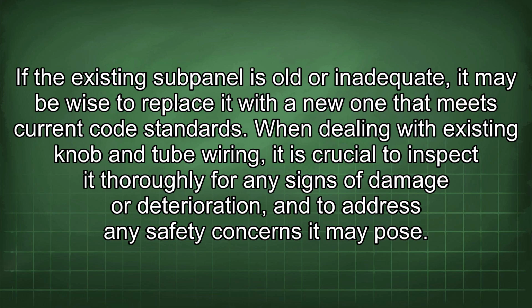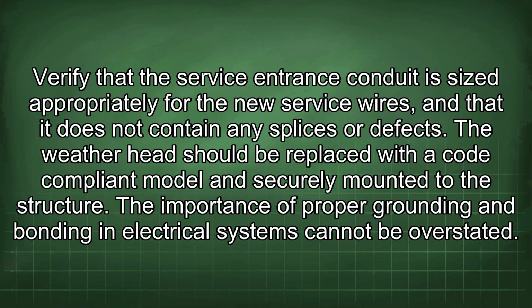When dealing with existing knob and tube wiring, it is crucial to inspect it thoroughly for any signs of damage or deterioration and to address any safety concerns it may pose. Verify that the service entrance conduit is sized appropriately for the new service wires and that it does not contain any splices or defects. The weatherhead should be replaced with a code-compliant model and securely mounted to the structure.